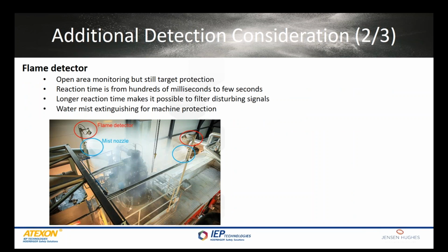The second additional detection consideration is a flame detector. This is applicable, for example, to receiving stations and other open area monitoring. It is also very good for machine monitoring. Reaction time is significantly longer than spark detectors, but still many times faster than smoke detectors. Typical reaction time is something like 3 seconds.